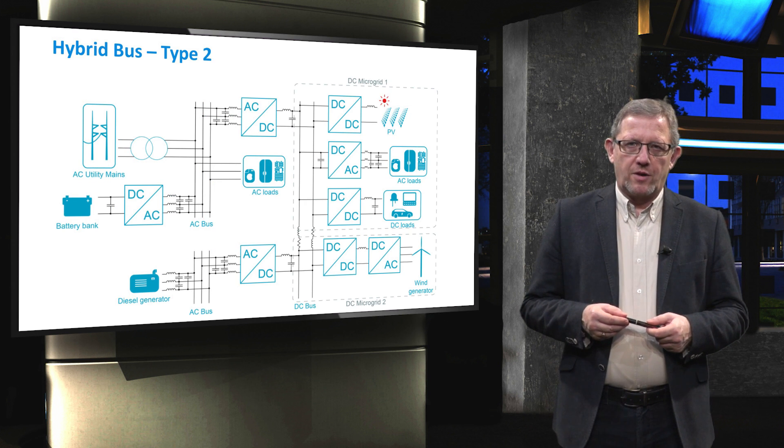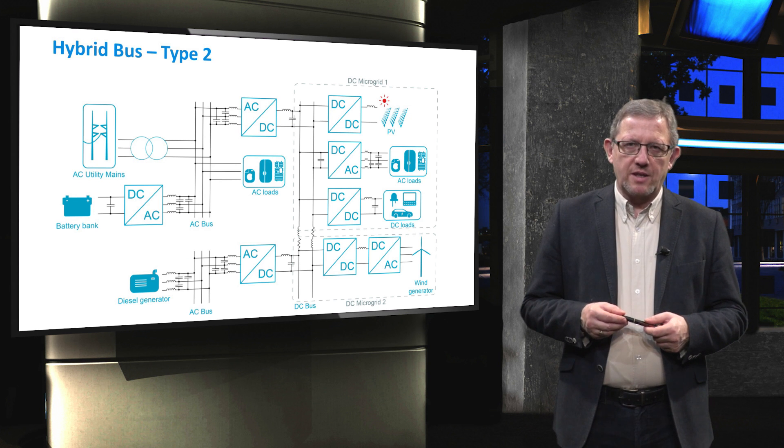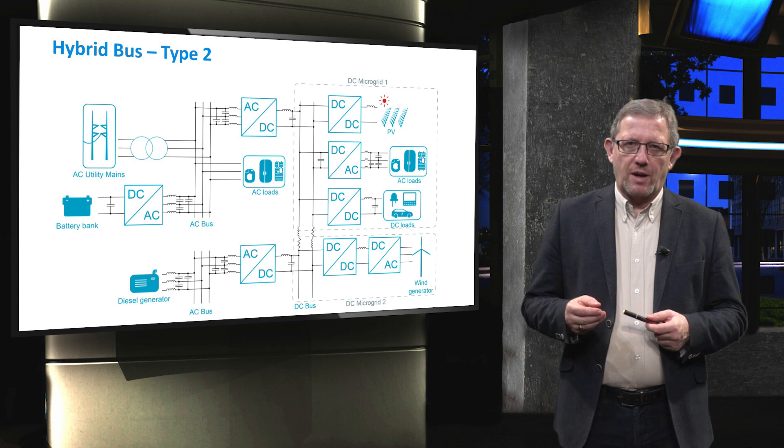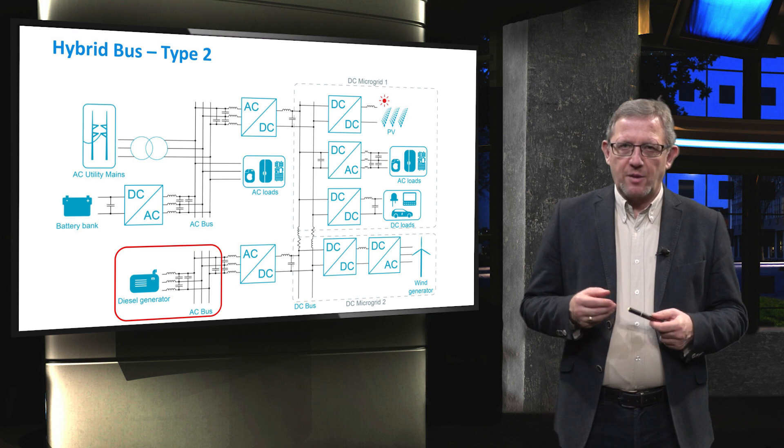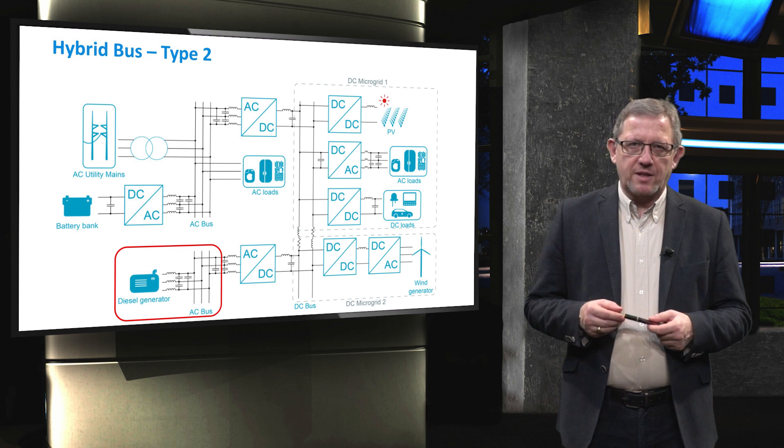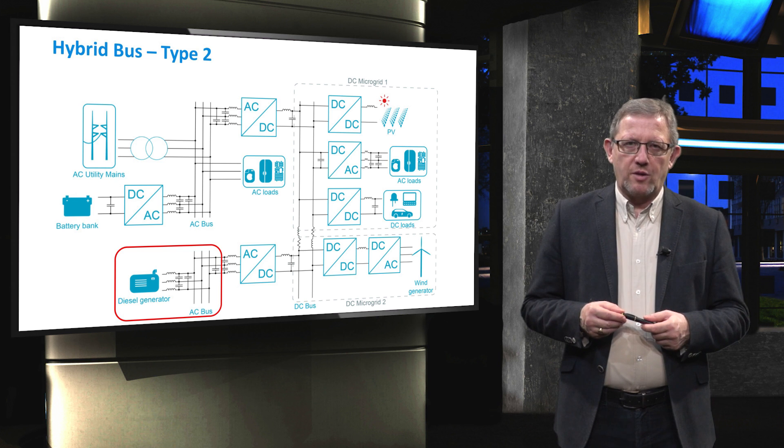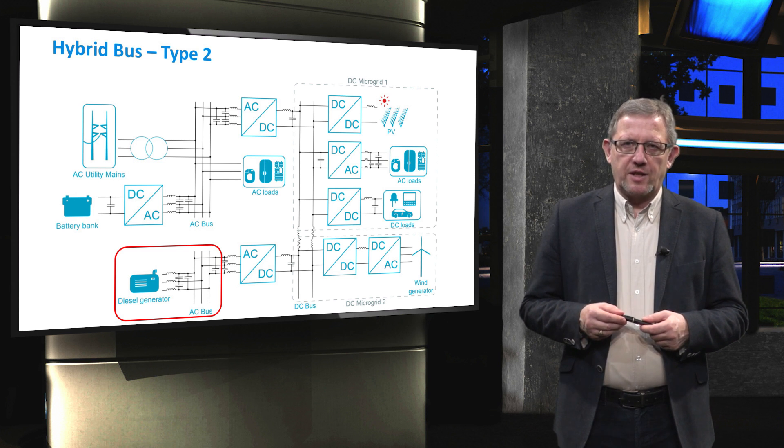To further increase the reliability, it is possible to create two AC buses where the diesel engine is seen as a backup for the DC bus. Thus, in the case of faults at AC utility mains or AC bus, still the DC bus can remain operational thanks to diesel through another AC bus.